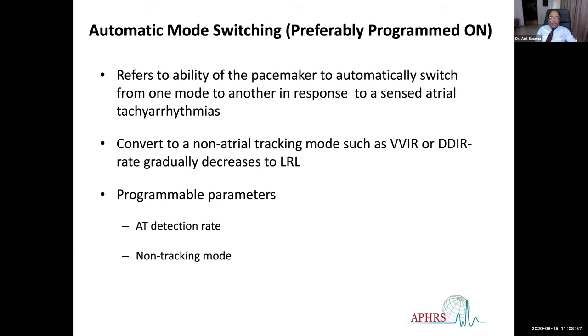So what is automatic mode switching? It is basically the ability of the pacemaker to automatically switch from one mode to another in response to a sensed atrial tachyarrhythmia. When we want to program this, we have to program two things: one, an AT detection rate, that is at what rate the pacemaker will implement the mode switch; and second, we want to decide on what non-tracking mode we want.